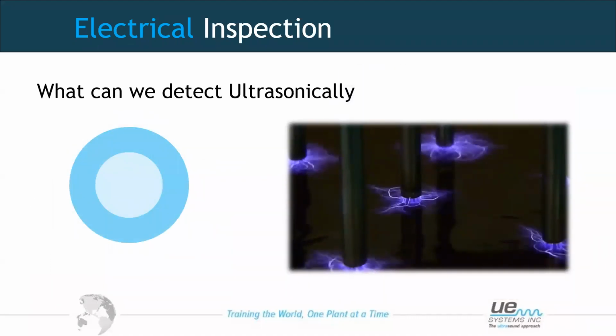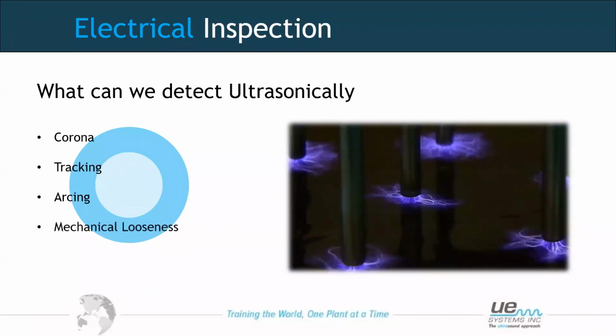So the things that we can detect with electrical inspections when it comes to ultrasound are things like corona, tracking, arcing, and mechanical looseness. Each of these will have their own sound characteristics. And because ultrasound is directional, we can pinpoint where these are coming from.